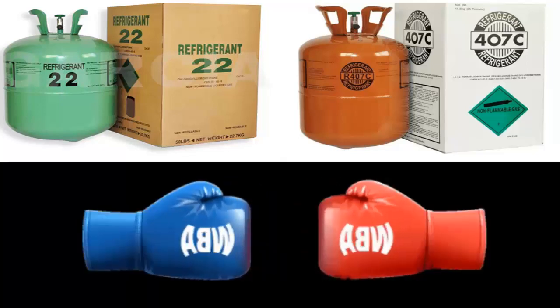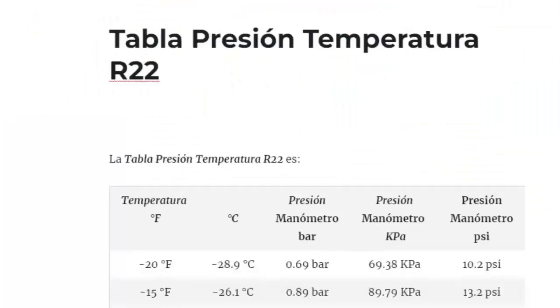The pressures of R-22 and R-407C are very similar. We can say that R-22 is a refrigerant that handles medium pressures. For a low temperature system, freezing to minus 20.5 degrees Celsius (approximately minus 5 degrees Fahrenheit), we need a pressure on the low manometer of approximately 20.1 psi, equivalent to 1.3 bars.